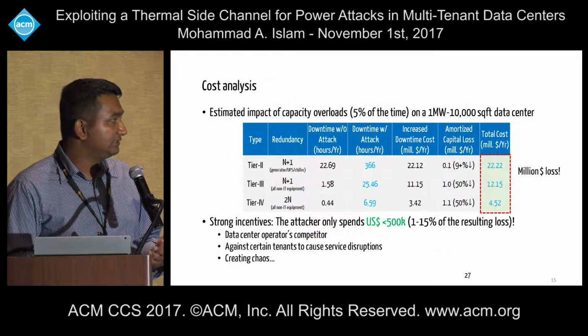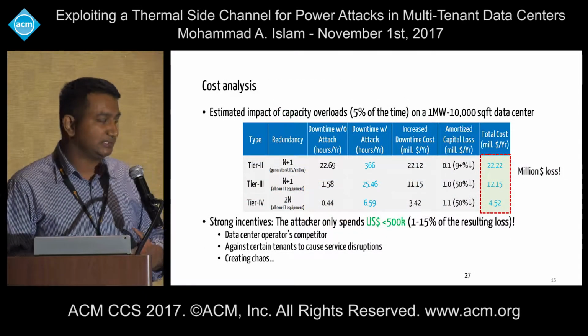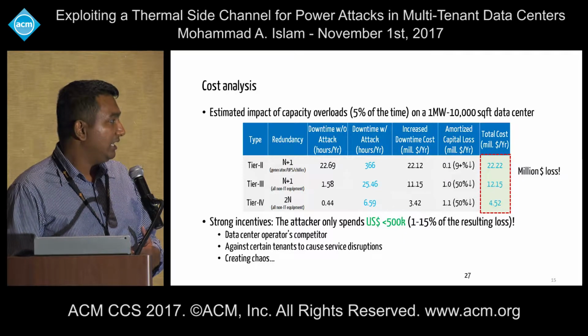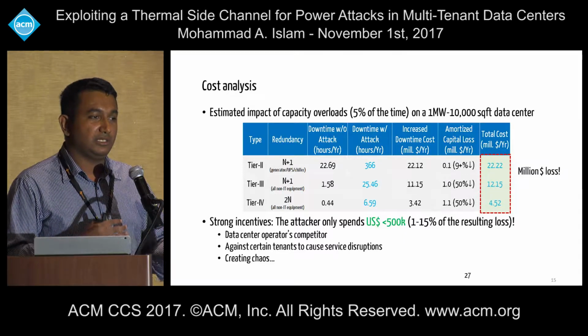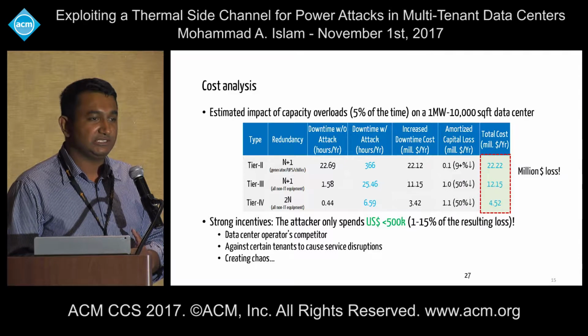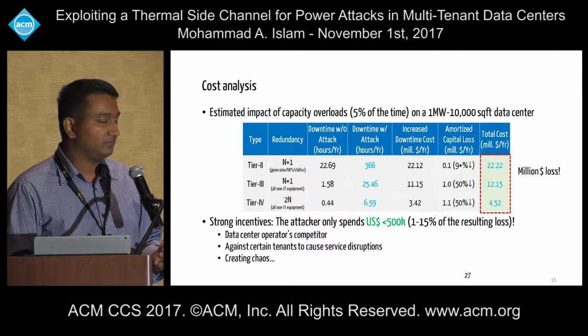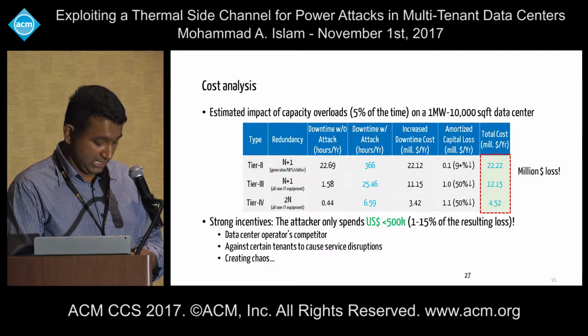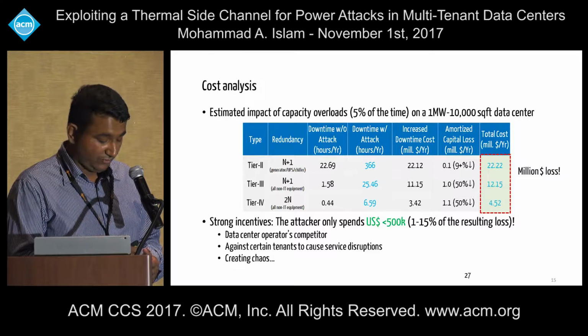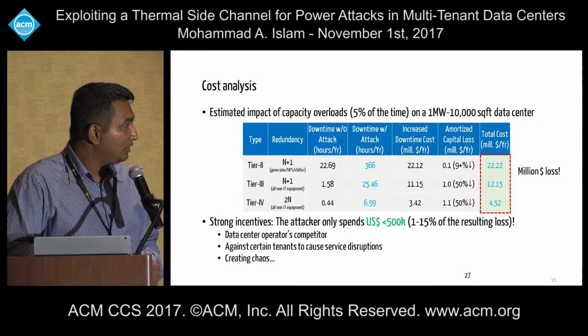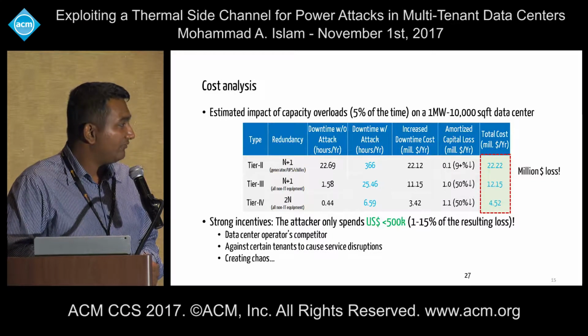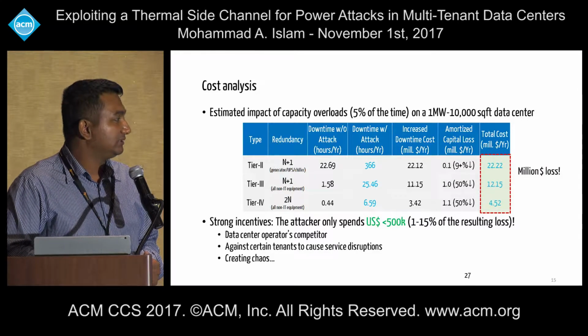We do some cost analysis of these power attacks on different types of data centers with different levels of redundancy. On a 1 megawatt, 10,000 square feet data center, where there is 5% time of overload, we can see that for a tier 4 data center, without power attack there is less than half an hour of outage, but with power attacks it can go almost to 7 hours.